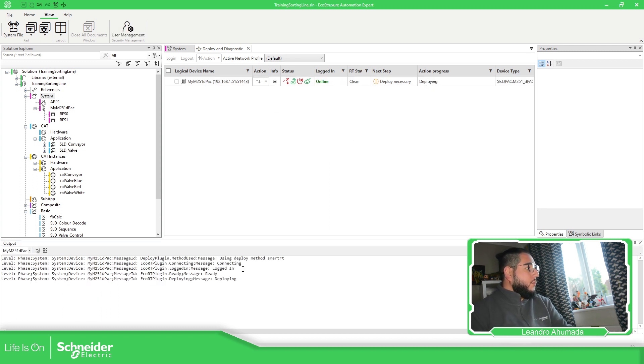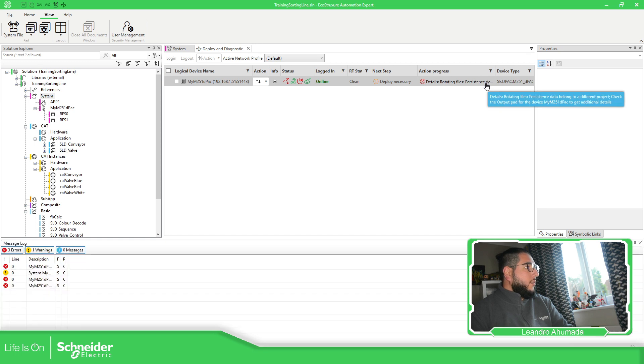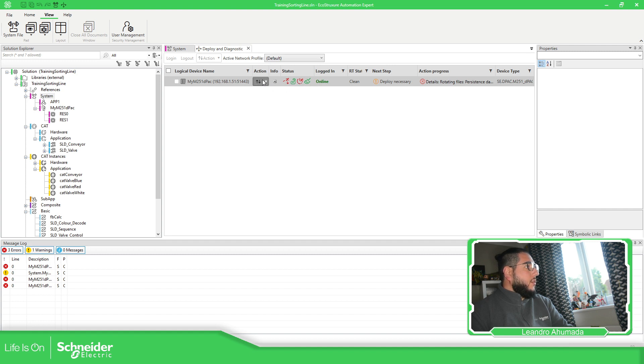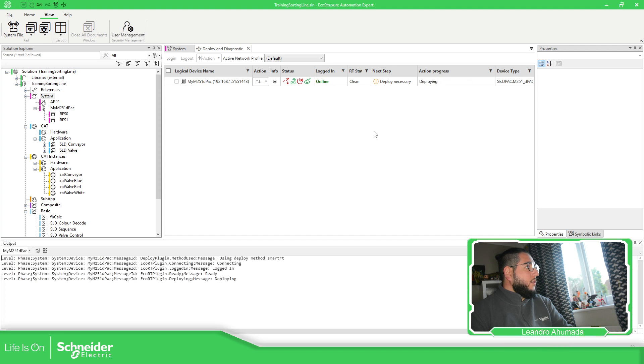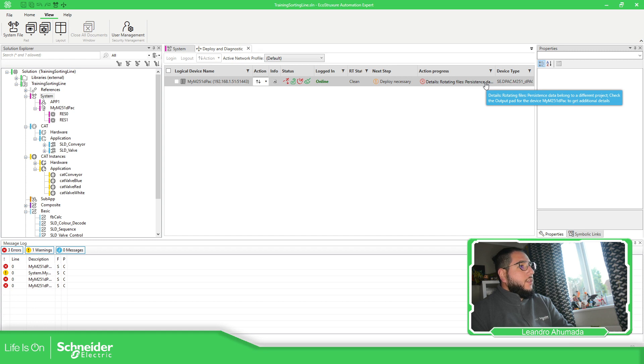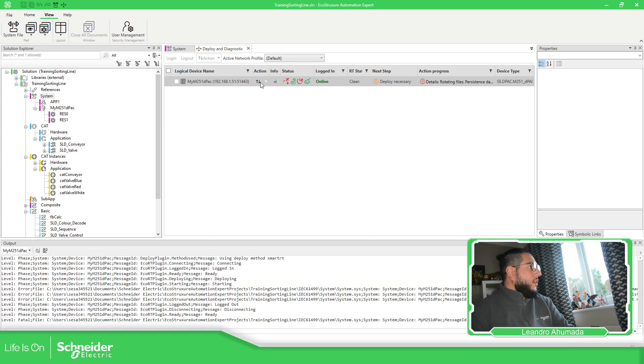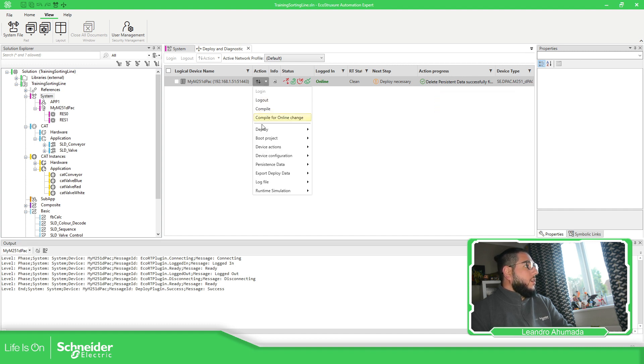It's doing something over there — it's starting. If we check system details, no problem there — it means a different boot project, so deploy is necessary. Deploying... In this particular case I'm not sure what was done in the previous one, but what we can do is delete persistent data. Delete persistent data — yes. Delete persistent data successful, so now the PLC is clean and we can make the deploy now.